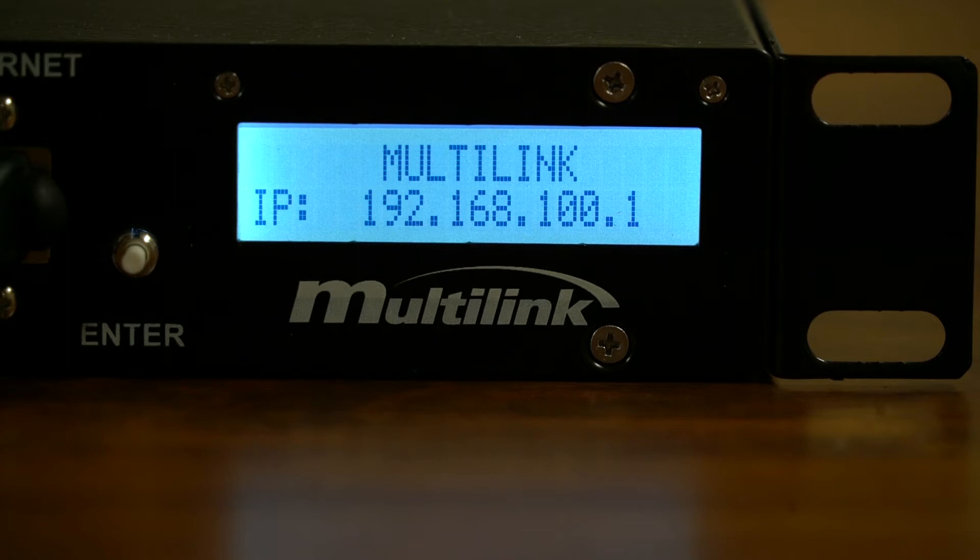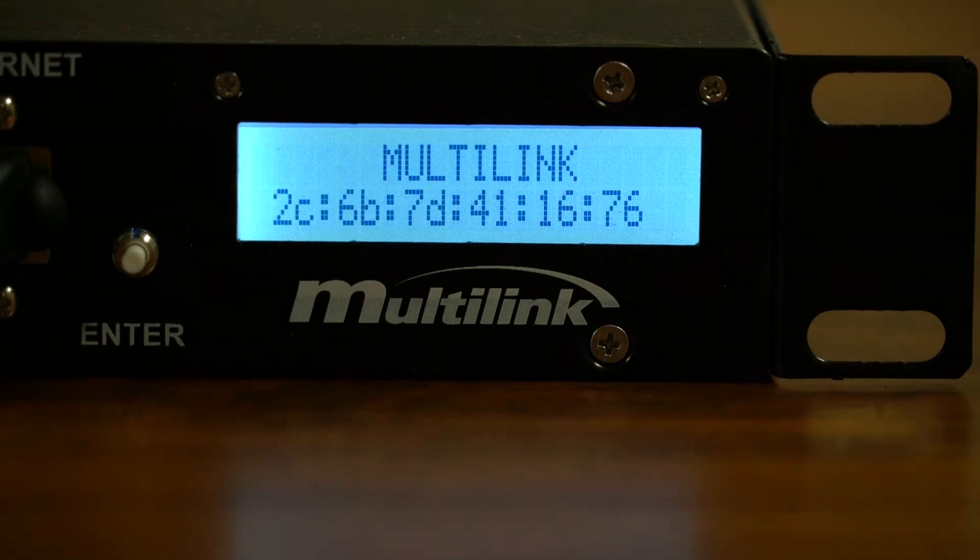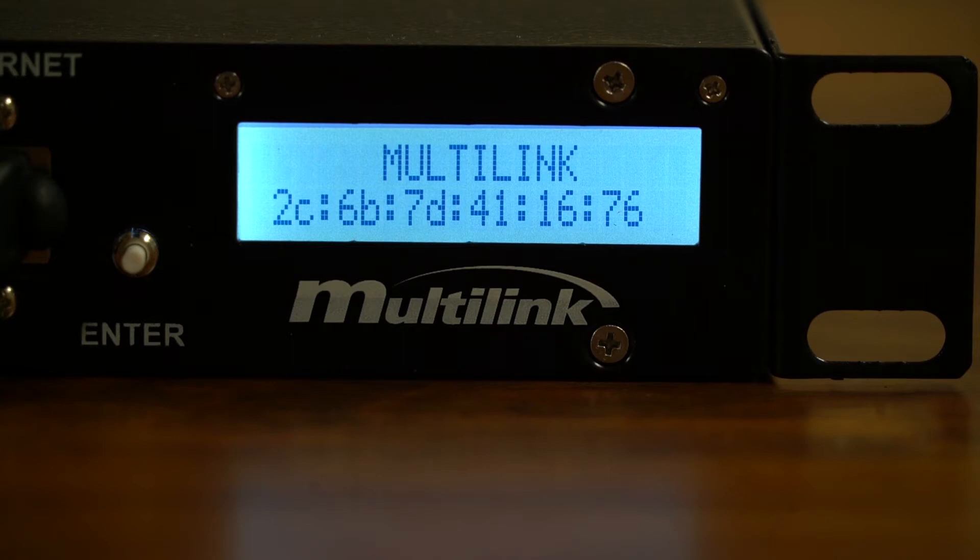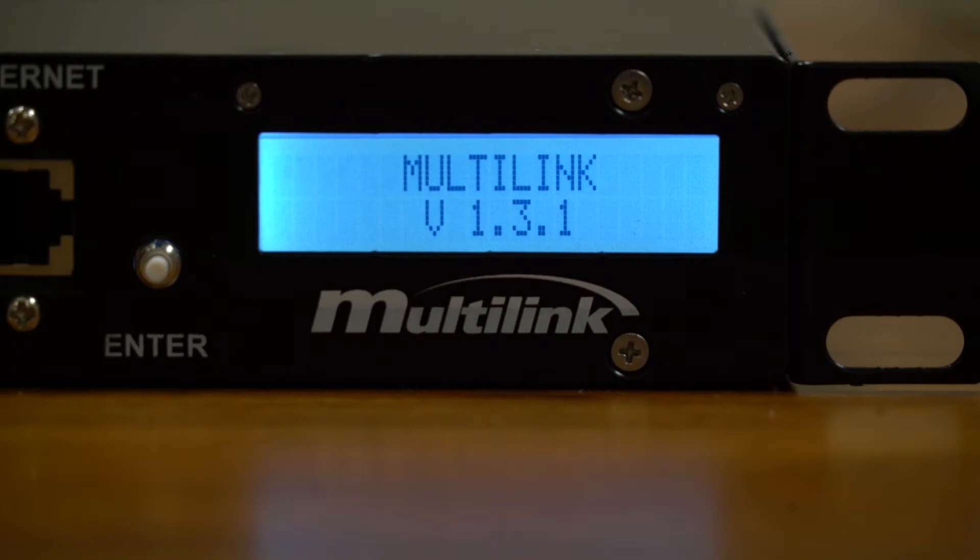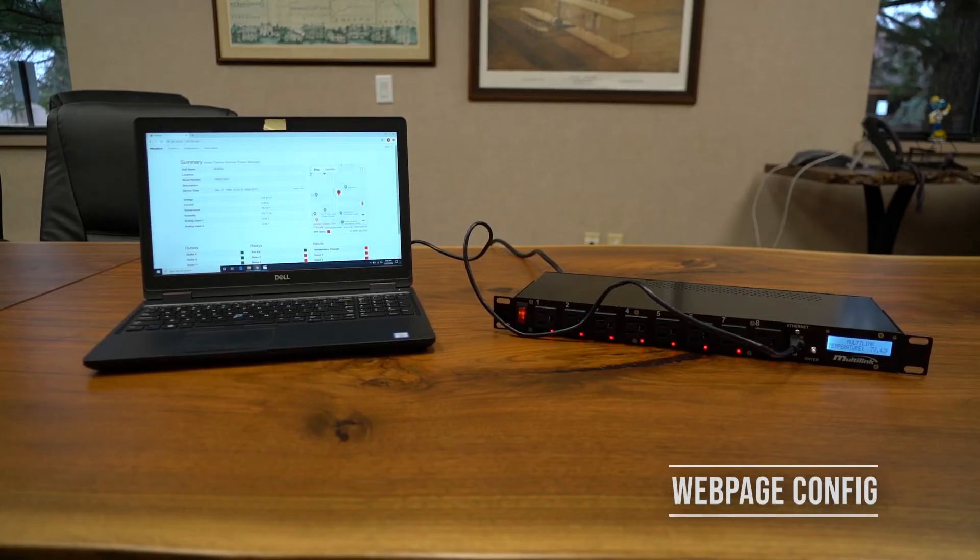The unit can be reset to the factory IP address of 192.168.100.1 by holding the push start button for 10 seconds and then releasing it. After IP naturally is a page showing the Smart Tracker's unique MAC address. Lastly the firmware version page displays the current firmware build number of the Smart Tracker.